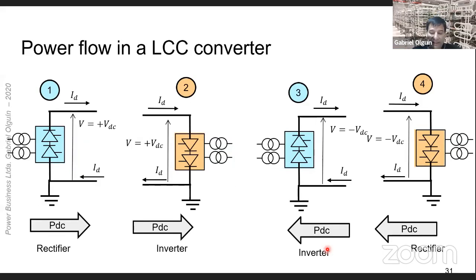We just saw that the LCC converter can produce a negative or positive DC voltage at the terminal of the converter by controlling the valves' ignition angle alpha. The DC current, however, can only circulate in one direction. It cannot change direction because the LCC valves are unidirectional. This slide shows some cases of DC link voltage polarity and power direction. Case 1 is a converter operating as a rectifier. Electric power is taken from the AC system and injected into the DC system. Case 2 is a converter operating as an inverter. Electric power comes from the DC link and is inverted in the converter and injected into the AC system.